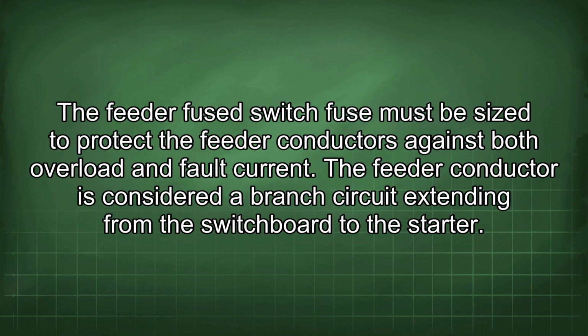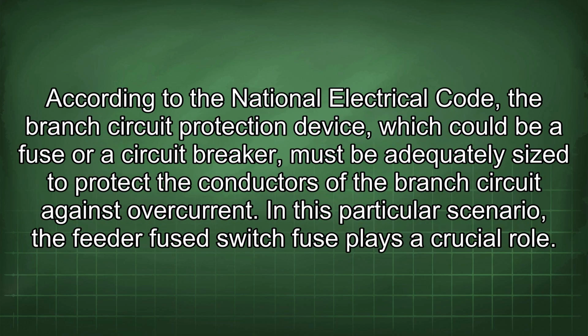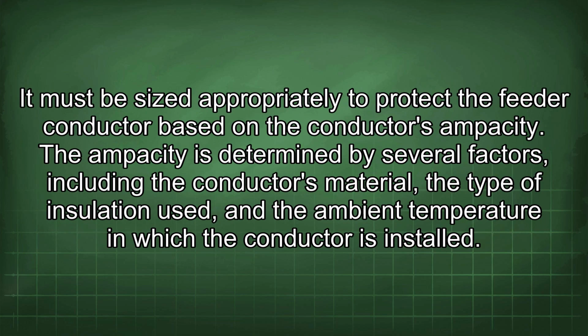The feeder conductor is considered a branch circuit extending from the switchboard to the starter. According to the National Electrical Code, the branch circuit protection device, which could be a fuse or a circuit breaker, must be adequately sized to protect the conductors of the branch circuit against overcurrent. In this particular scenario, the feeder fused switch fuse plays a crucial role. It must be sized appropriately to protect the feeder conductor based on the conductor's ampacity.